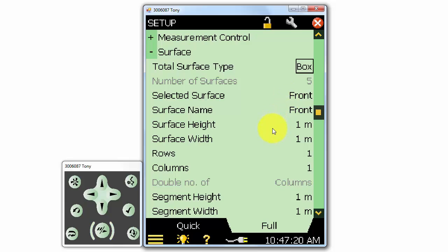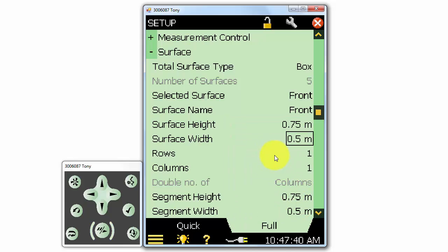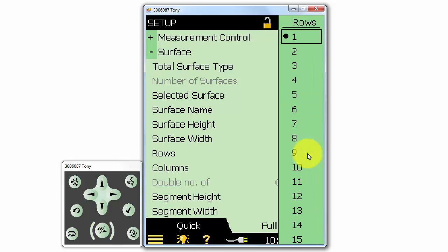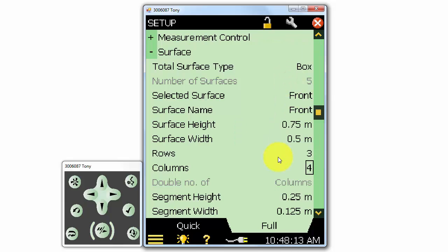I'll enter the correct measurement surface height and width so the sound power calculation is based on the correct area of the measurement surface. For this demonstration, I'll measure close to the surface of the sound source in order to make an intensity map. We can select a number of rows and columns for each surface to subdivide the measurement. Most standards only require one segment per side, but if we want to make a noise map, we'll need to select multiple rows and columns. You should select at least three rows and three columns for sound mapping. If you select more segments, your measurement will take longer, but you'll achieve better spatial resolution on the noise map.